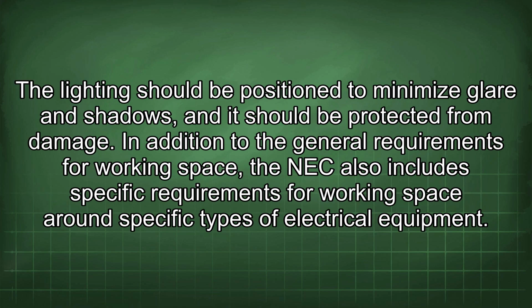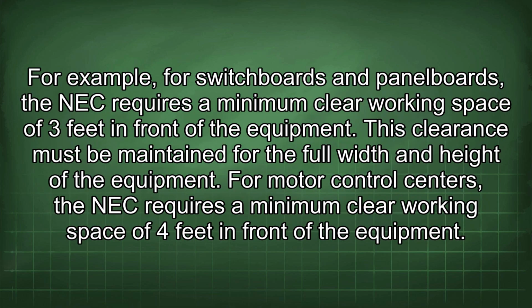The lighting should be positioned to minimize glare and shadows, and it should be protected from damage. In addition to the general requirements for working space, the NEC also includes specific requirements for working space around specific types of electrical equipment. For example, for switchboards and panel boards, the NEC requires a minimum clear working space of 3 feet in front of the equipment. This clearance must be maintained for the full width and height of the equipment.